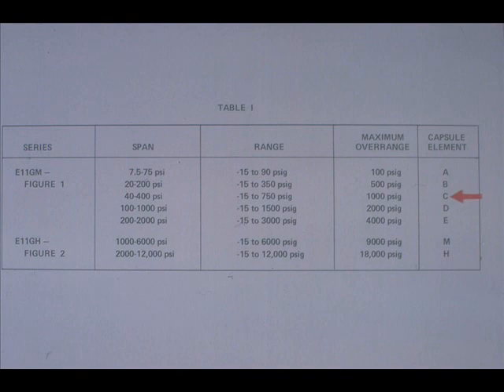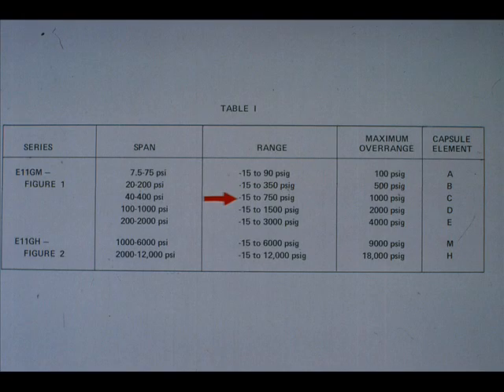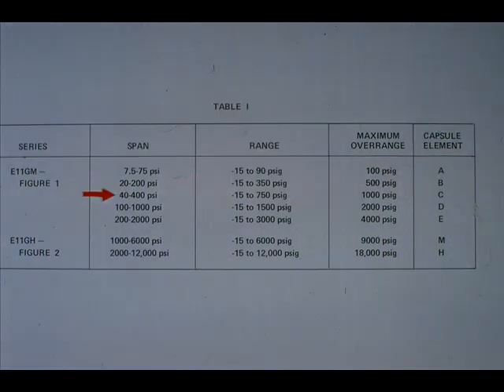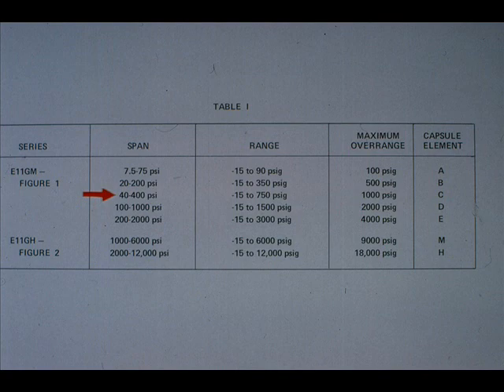Now let's have a look at capsule C. The range limits are minus 15 to 750 PSIG. The span limits are 40 to 400 PSI. Both range and span limits are within our 100 to 200 PSIG range. Therefore, either capsule B or C could be used.